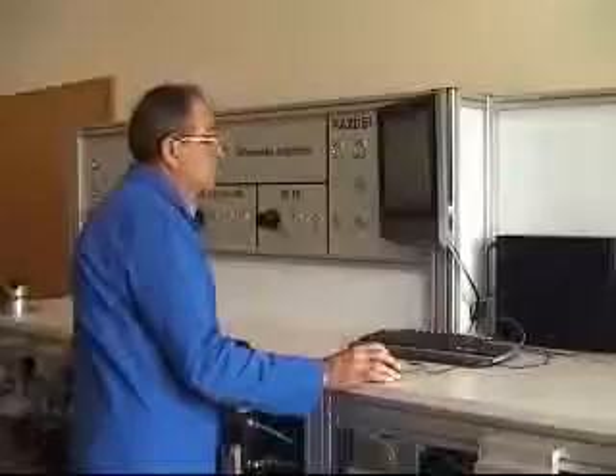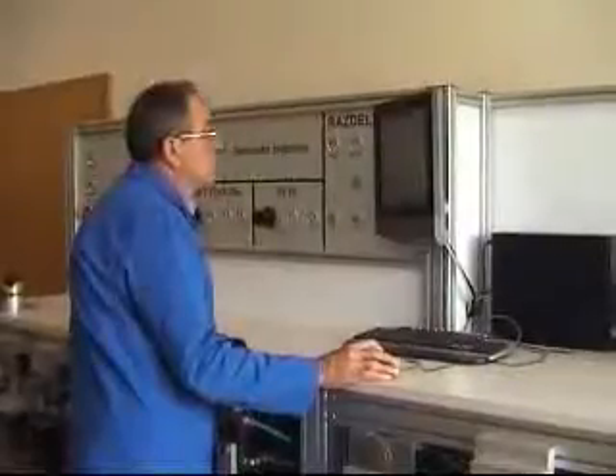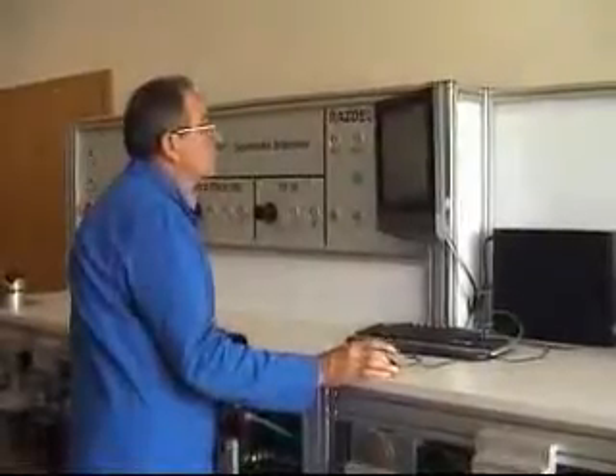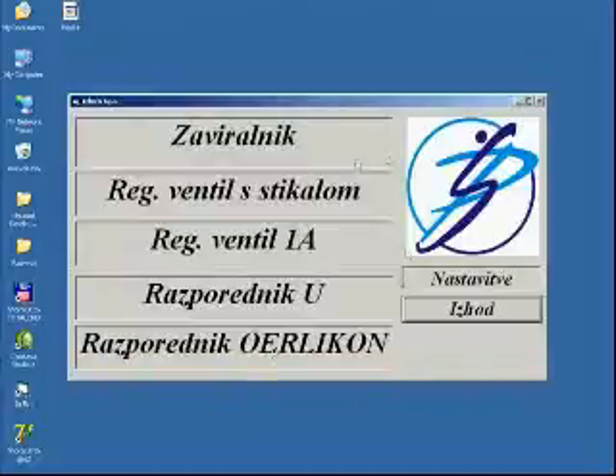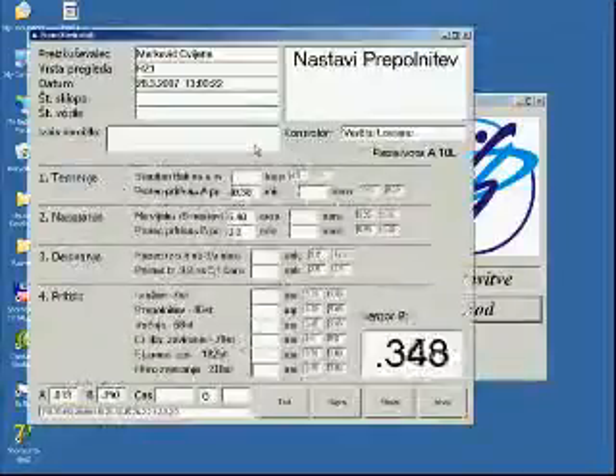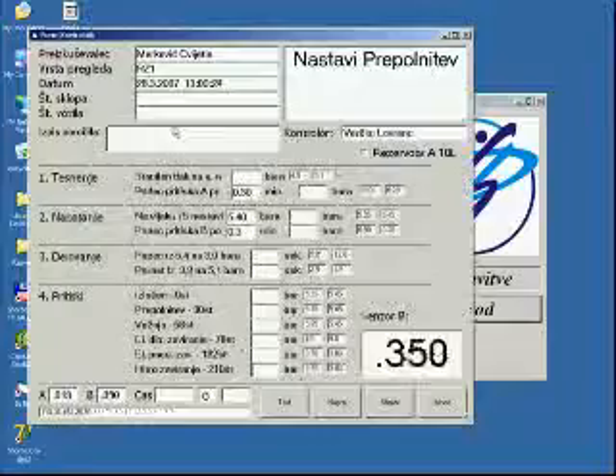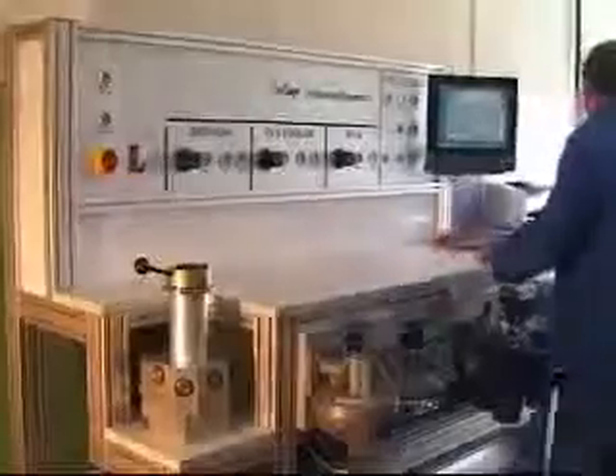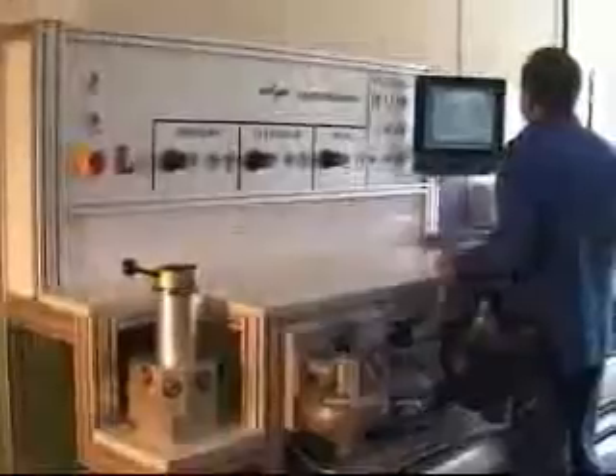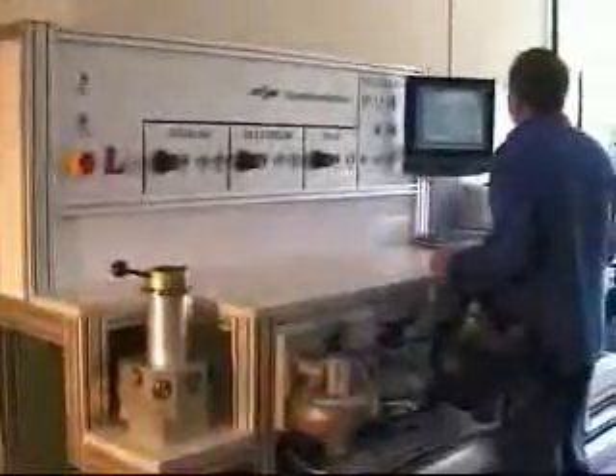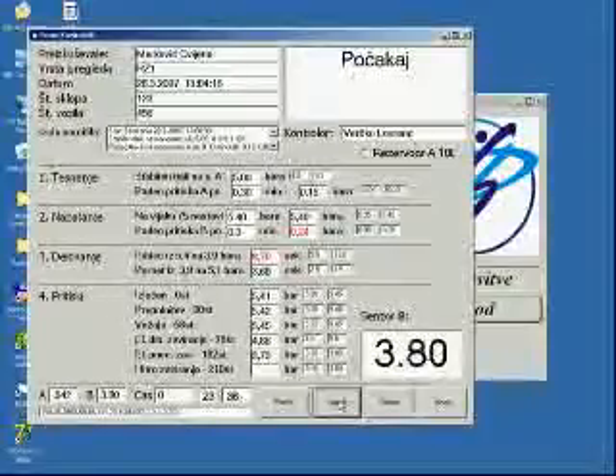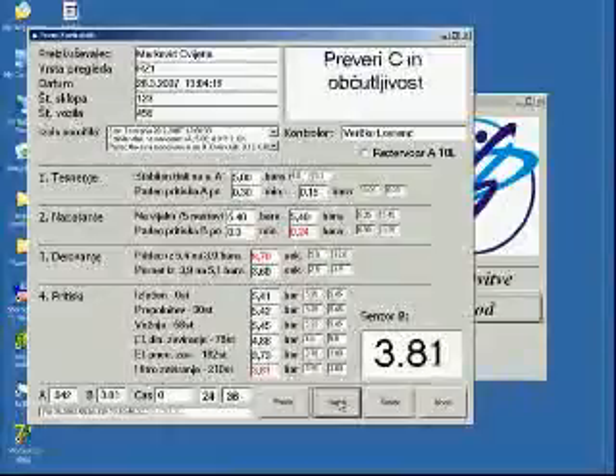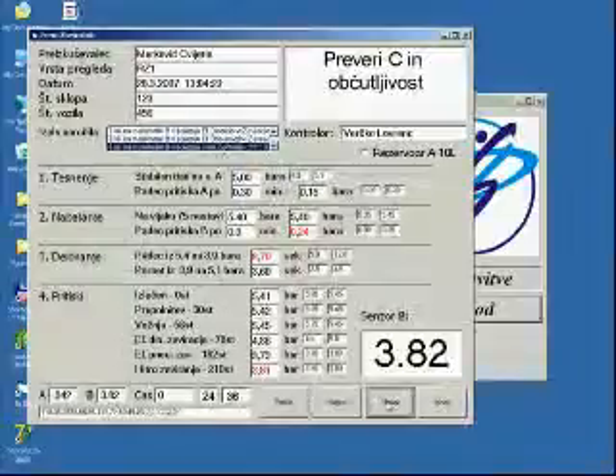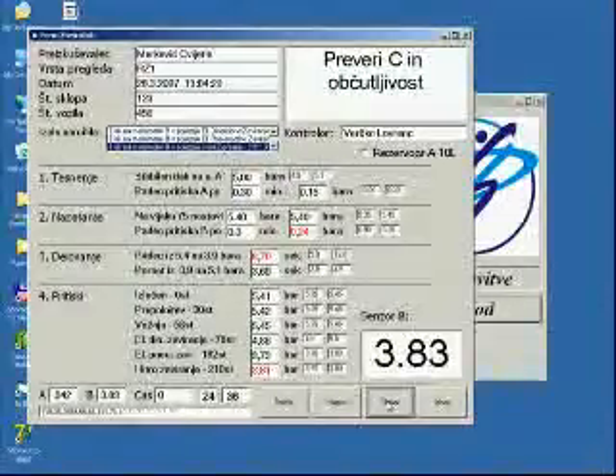The operator selects the appropriate test procedure. After being started, the test is performed automatically. If the operator's intervention is necessary, the device will hold, display a message indicating the action required. After these actions have been performed and confirmed, the automatic testing is continued. After the completion of the procedure, the test results are stored in a database and a test report is printed.